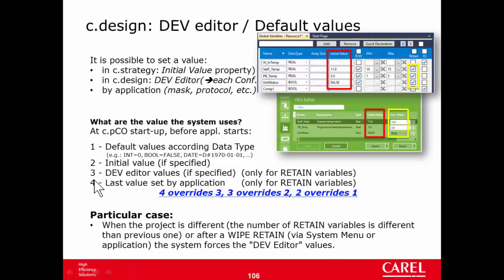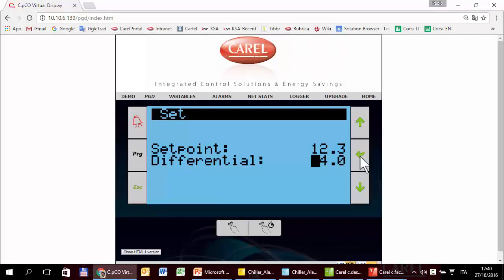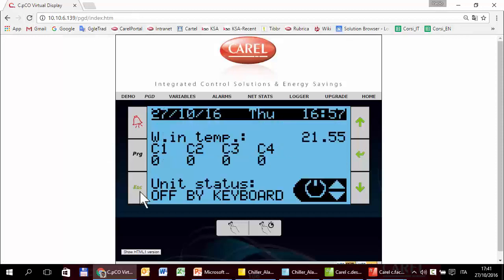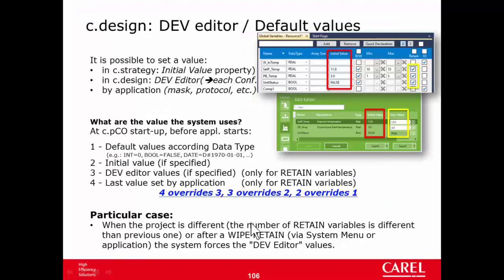Now let's trigger the last use case — the last value set by application. We have seen this many times. We change the setpoint to 12.3, then power off and power on, and I expect the setpoint back to 12.3. The controller is starting. Here it is — the setpoint is 12.3, exactly as expected. So we have tested this part as well.